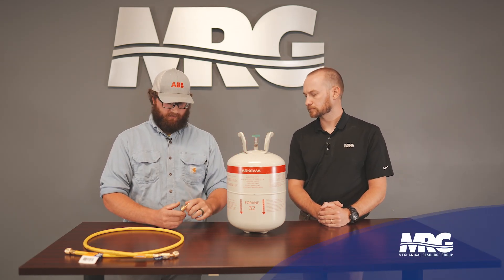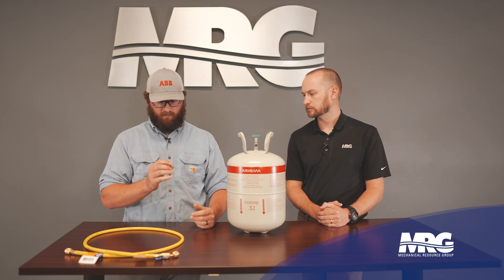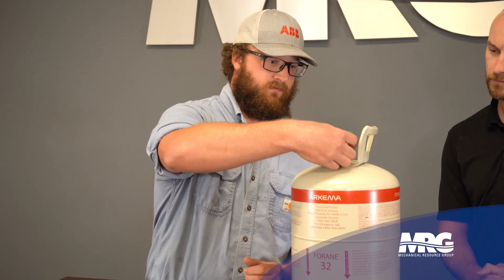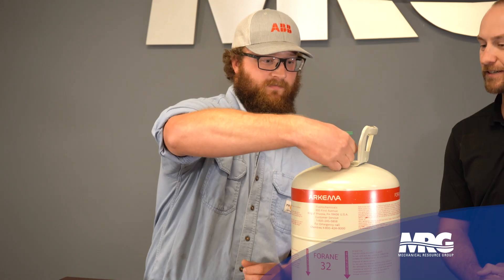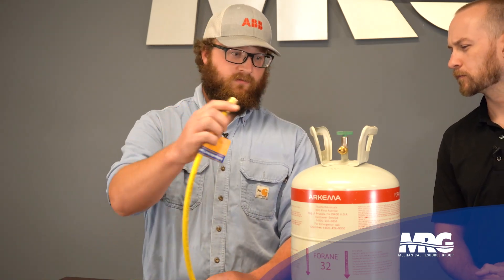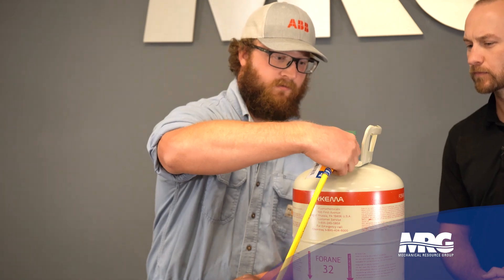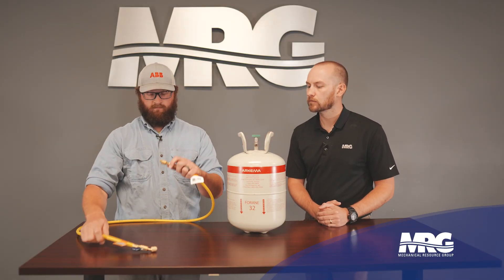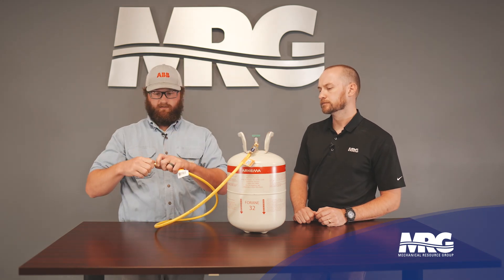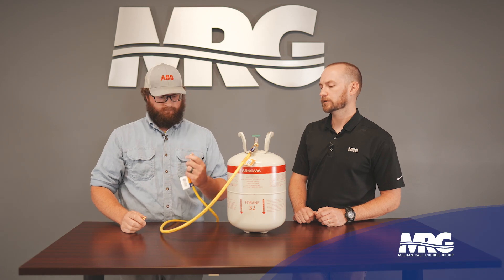I have a couple things here from Yellow Jacket. I have a left-handed thread to male quarter-inch normal thread to go to your regular hose. Basically, you're going to put it on there left-handed, just like your acetylene torch, and then you can take your other end of your hose and thread it on as you always did. They also offer a whole hose — one side you're still going to have your ball valve like on most of your Yellow Jacket hoses, but you're going to have your left-handed thread adapter that will go onto the tank, and then you can hook the other side up to your regular manifold gauge set.